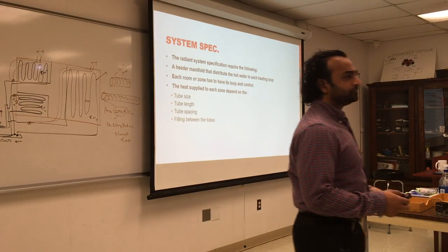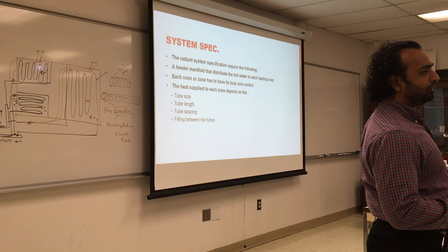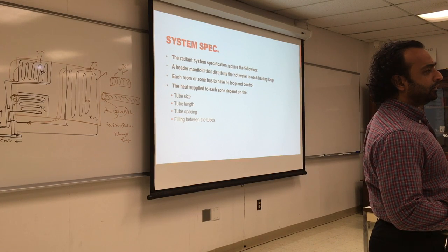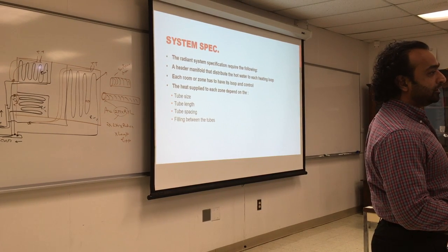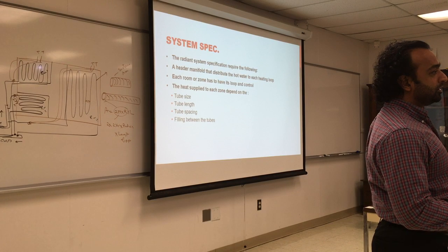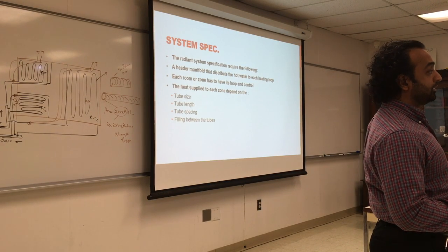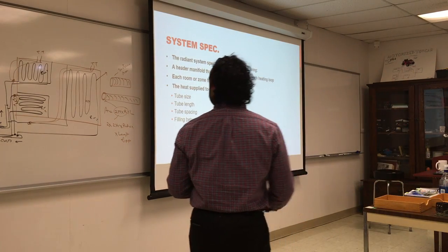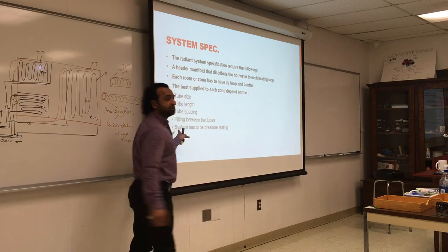Well, the more pipe you have, because it's radiant floor, you have a lot more pipe, would that need a bigger expansion tank, or more than one? Yes, that's actually a good question. The expansion tank will always have to accommodate the expansion of the entire water in the system, and we'll talk about that piece of the calculation. So, the system has to be pressure tested over time.